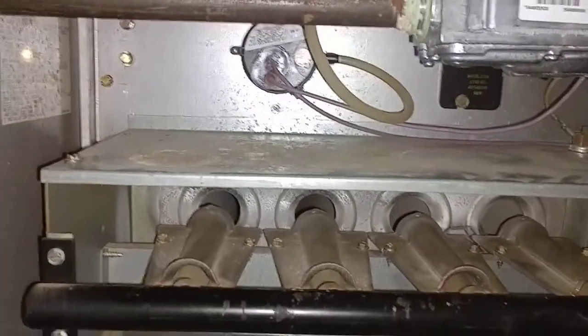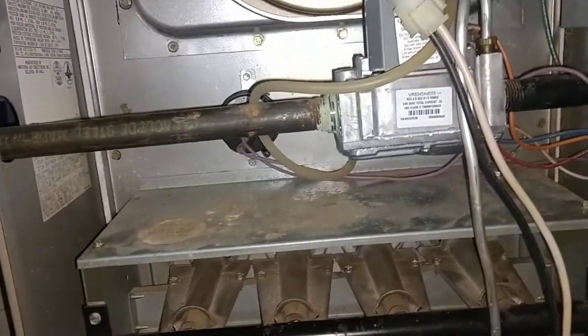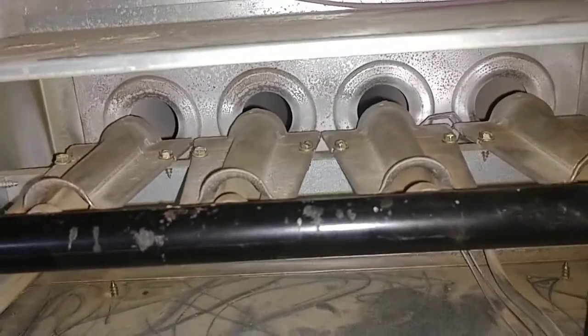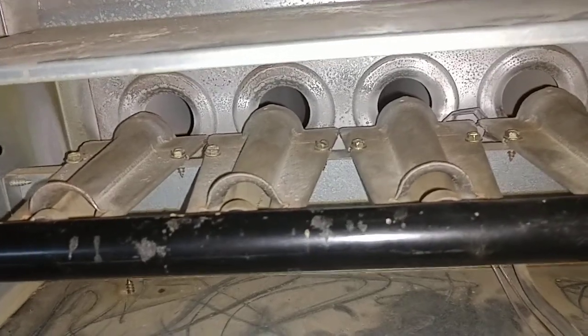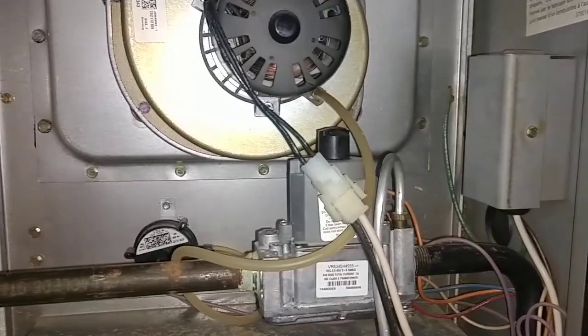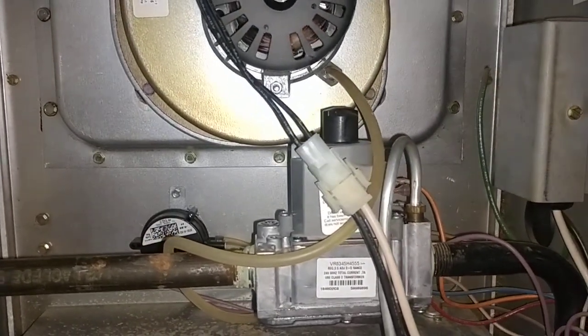Now this furnace is running 100% perfect. It's got a new motor in it. I cleaned all these out anyway, but none of it mattered. It's got a new control board — this thing's going to be rolling for quite some time. There are a lot of simple things you can miss. Thanks for watching and I hope this helps somebody. This only takes like 15 minutes if you know what you're doing, and it's a good thing to do every year anyhow. Always check these rubber hoses for deterioration or cracks — they're easy and cheap to fix before you have a furnace technician come out and pay a lot of money. I hope this helps.